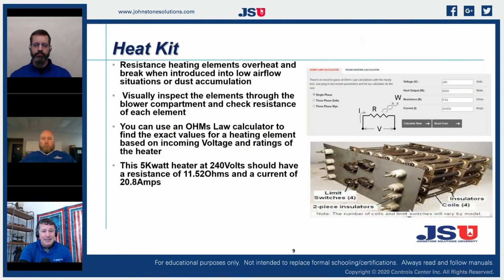When we get into our heat kits, we can actually check the resistance of those things. So if we take a heat kit, we can use our same Ohm's law to figure out how many ohms is going to be going across that heater. So if I had this particular heater and it was a 5 kW heater, and I knew that I have 240 volts for that sucker, I could actually disconnect one lead. I typically do one. You can do both of them if you feel more safe about it, but you can disconnect that one lead so we can isolate our element, put our meter on ohms, horseshoe setting, remember?